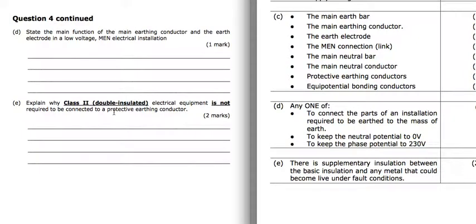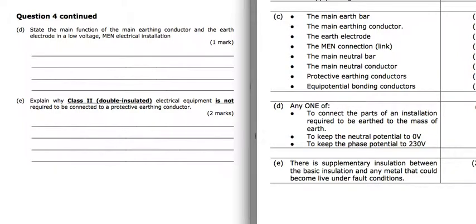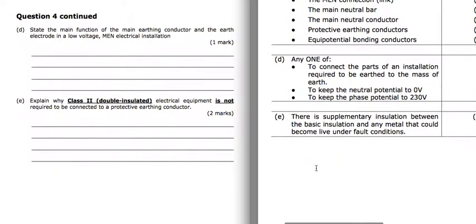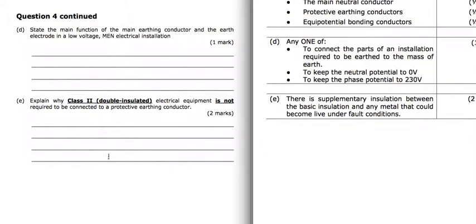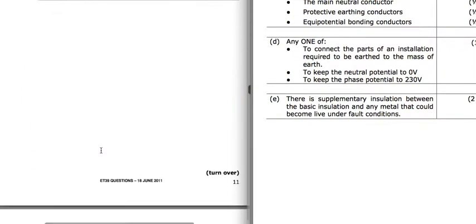Explain why class 2 double insulated is not required to have a protective earthing conductor. Well, we don't need it because there's supplementary insulation between the basic insulation, so that's the cables, and any metal that could become live under fault conditions. So there's another barrier after those cables. There's 2 parts of insulation. It makes it a class 2 double insulated.